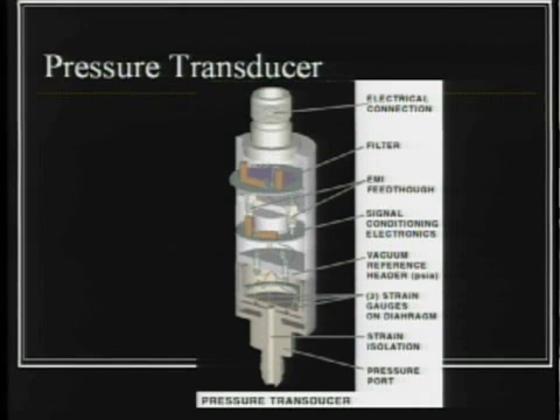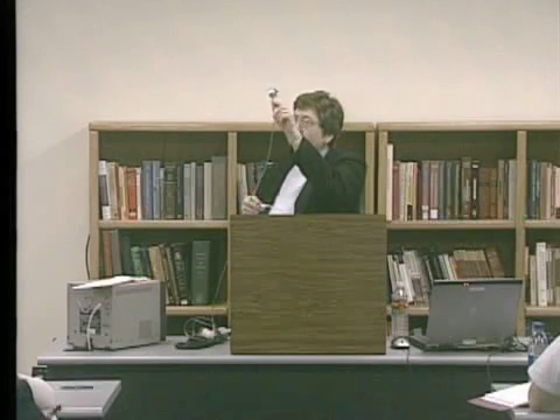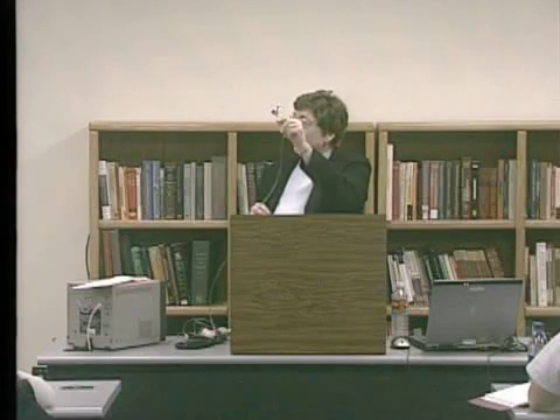So the pressure transducer is actually a fairly simple little device. This is an example of one. You can see that it's not very big. And this is the pressure transducer itself, which isn't going to do us much good because we have no way to connect it to the airway at all yet. So that's why we attach a sensing tube to it. And the sensing tubes don't really get in the way very much for the kinds of tasks that we do. So usually somebody's doing like a pa-pa-pa, and the tongue tends to stay out of the way.